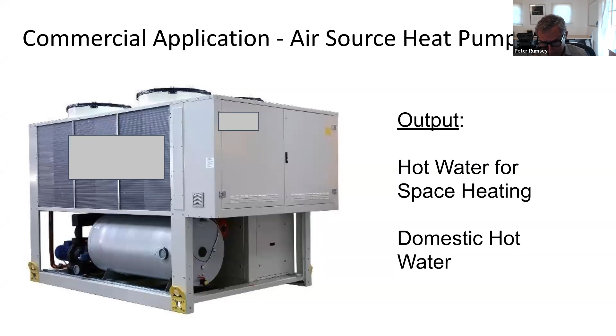There's heat recovery chillers, used at small and large scale, where if you're in a building that's doing cooling and also needs heating, we can take the waste heat from the cooling and use it for heating the building. A good example is a building with a lot of labs, computer rooms, high intensity areas, meeting rooms, or classrooms. They all need cooling, but you might need heating for domestic hot water, or on the north side of the building on a cold day where it's losing heat.